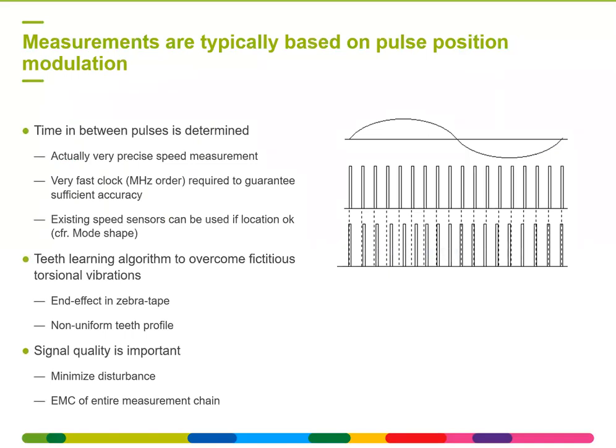Well, torsional vibrations is typically a measurement which is based on pulse position modulation. On every shaft line, you have a speed sensor to be able to determine the speed at which your machine is running. And actually, this speed sensor is also typically used as a torsional vibration sensor. It is typically placed at a toothed wheel. And what you do is every time a tooth passes, you generate a pulse. So in the end, you have a pulse train, as you can see on the right.